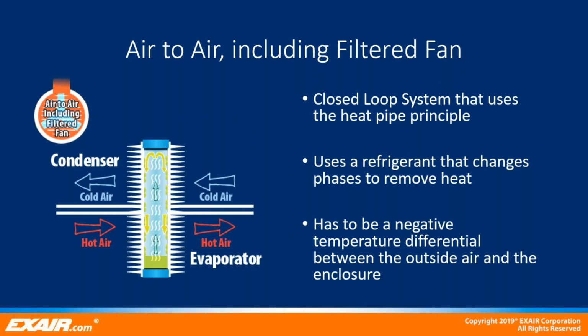The lower section of the heat pipe assembly is in contact with the heated air from the electrical enclosure. This heat causes the refrigerant to change phase and vaporize. That vapor then flashes to the top of the pipe, which is in contact with the outside air. When the outside air temp is lower than the enclosure temp, the refrigerant vapor gives up the heat to the outside air and returns to a liquid. The liquid then falls to the bottom and the cycle starts again, as long as there is a negative temperature differential between the inside and outside air.